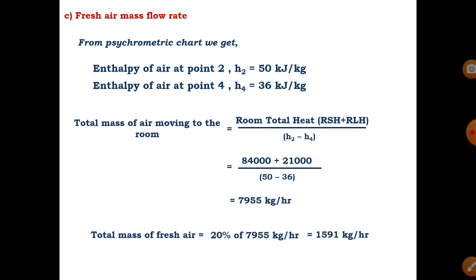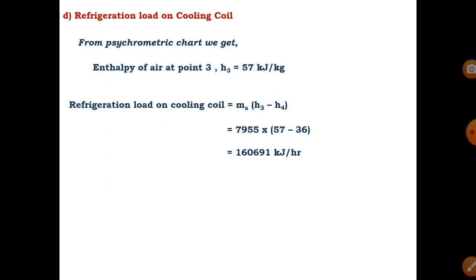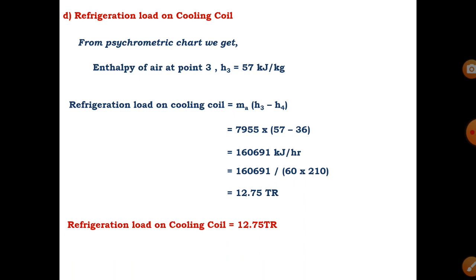Fresh air mass flow rate is 1,591 kg/hr. For the last part, calculate the refrigeration load on the cooling coil (process 3 to 4). The total mass of air through the cooling coil is 7,955 kg/hr (sum of fresh and recirculated air). Refrigeration load = mass × (H3 - H4) = 1,60,691 kJ/hr. Dividing by 60 and 210 converts to tons of refrigeration, giving a cooling coil refrigeration load of 12.75 TR.